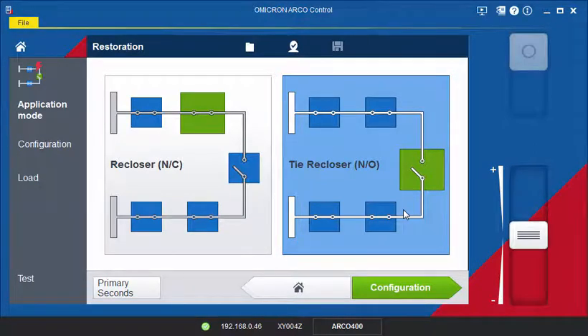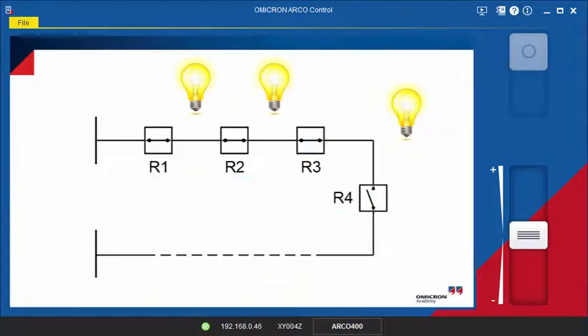Let's have a look at a typical application for such a test. This is an open ring feeder with several reclosers. R1, R2 and R3 are line reclosers which are normally closed during operation. R4 is a tie recloser which is normally open. There is no communication between the reclosers.